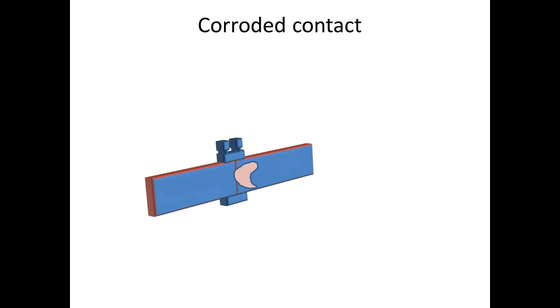In industrial areas, some conductors are affected by corrosion. If a corroded conductor is connected in the joint, the joint area will have high resistance since there is no perfect joining. The current flow will be restricted over this corroded area, which can be found by doing contact resistance testing.